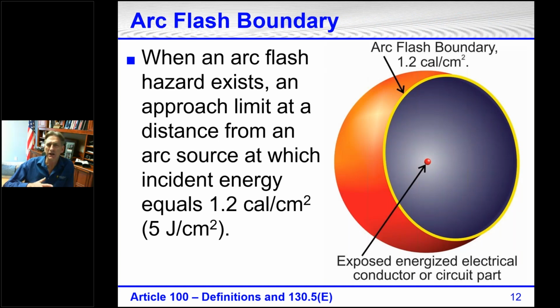And for shock, we've got to determine, all right, if we're going to be crossing the restricted approach boundary, we're going to have to protect ourselves. And what that is going to mean is rubber insulating gloves with leather protectors. That's going to take care of shock. Arc flash boundary involves more clothing and equipment.